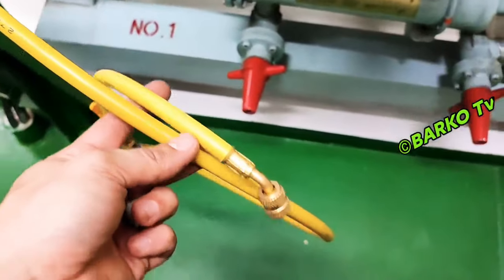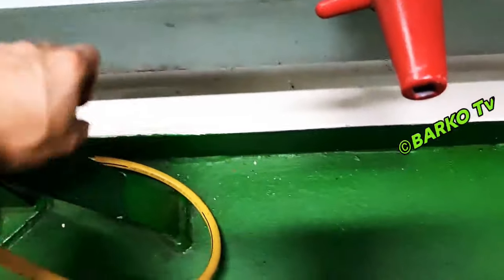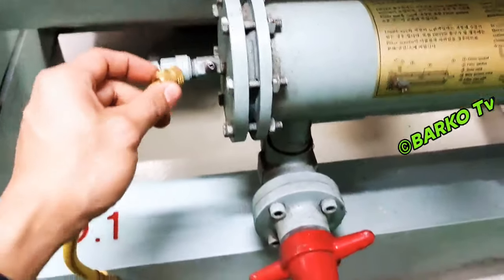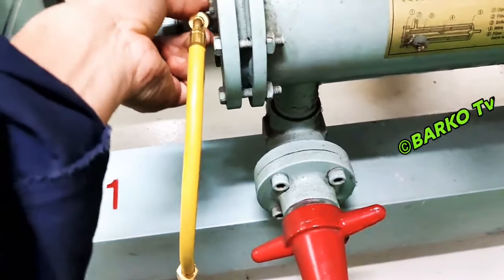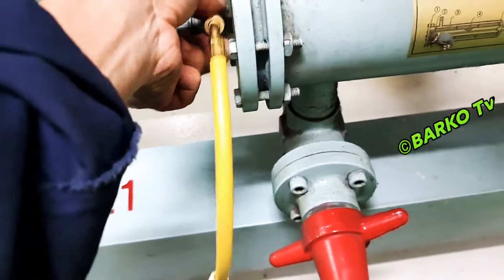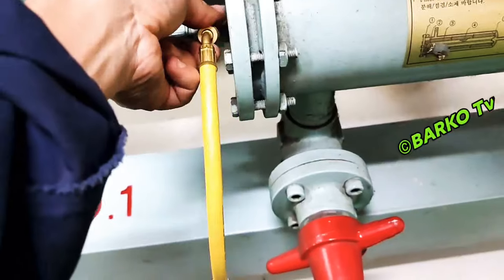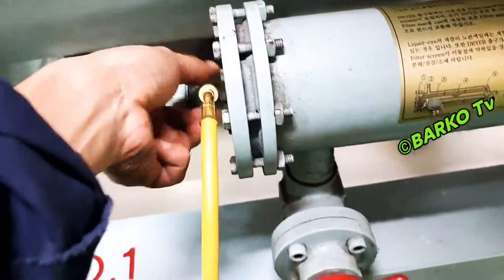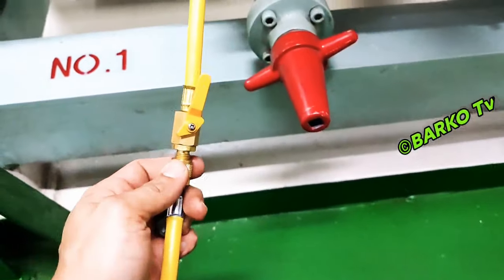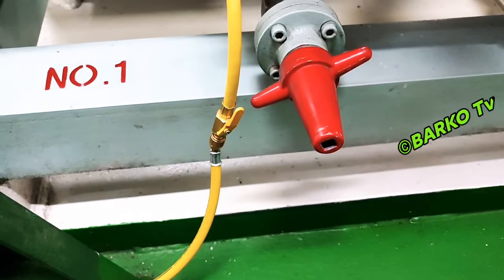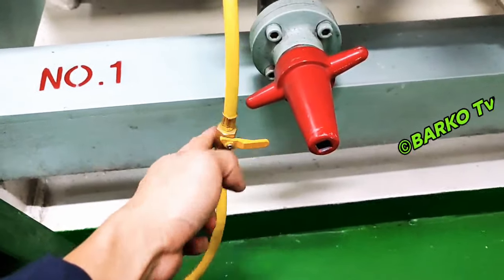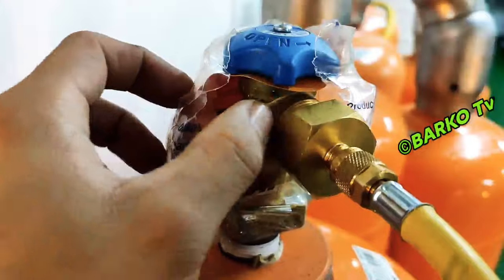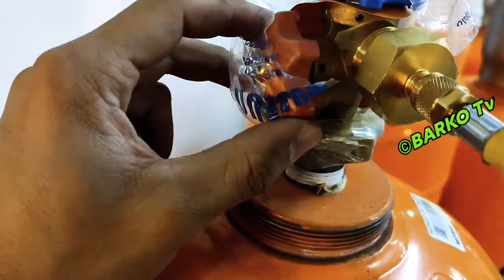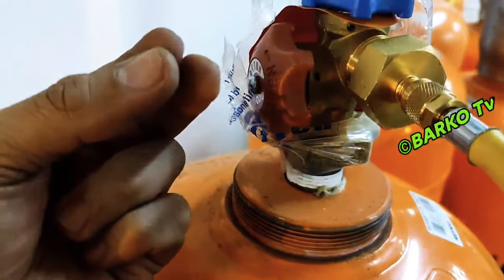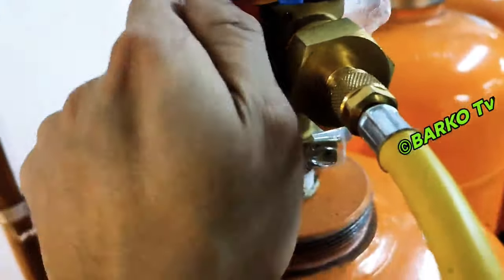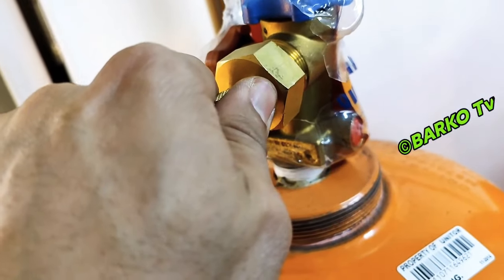At the end, you connect to the isolation valve. Isolation valve for the charging line. This is the charging for liquid refrigerant. This is located before the filter dryer. All connectors are hand tight. Slightly open to bleed, or to purge, the air.